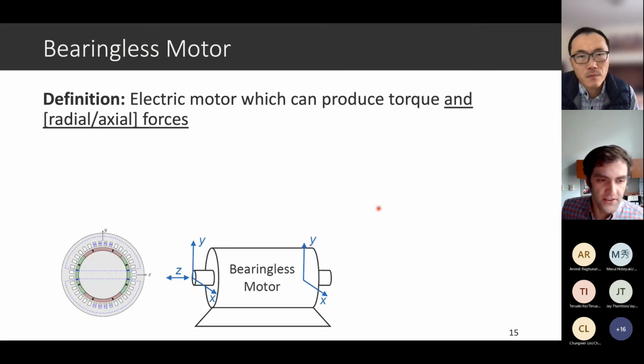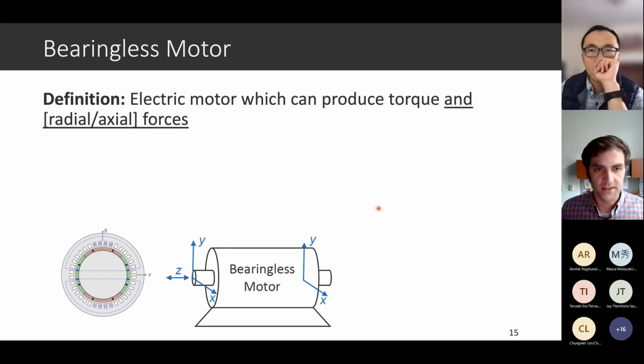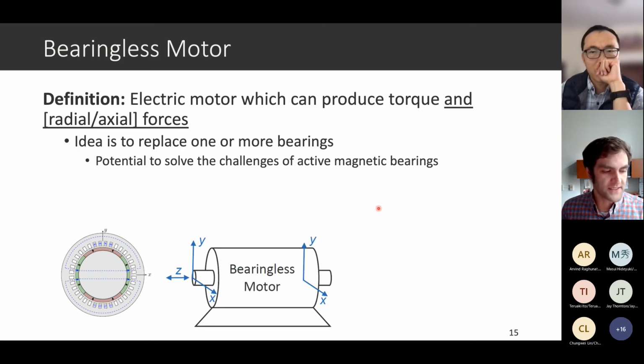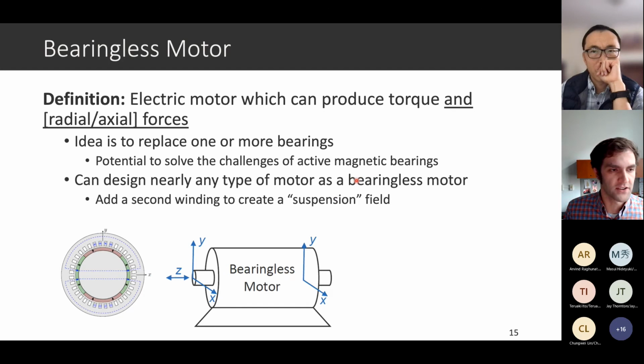Okay, so that was active magnetic bearings. The other technology, where most of the research is right now, is bearingless motors. A bearingless motor is an electric motor that produces torque, as motors normally do, but in addition it can also produce radial or axial forces. The idea is you use the same steel of your motor, but modify the magnetic field so it produces force as well as torque. You can use this to make your motor behave as a bearing and replace one or more of the system's bearings, eliminating them entirely. This has potential to solve a lot of the challenges of magnetic bearings, which we'll talk about later. For now, let's focus on the higher level story.